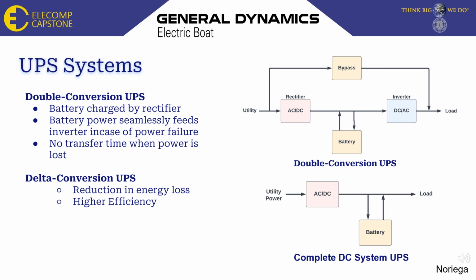What we opt for is a complete DC system. This means our UPS will run utility power through a rectifier to power both the load and the battery. This would mean there's no need for a bypass, as power would follow the same path in any circumstance. The great benefit of this UPS system is that it should improve power quality and allow for greater scalability, as DC power is easier to work with, since fewer components are needed and there's no need to worry about harmonics, load balancing, and other drawbacks of AC power.